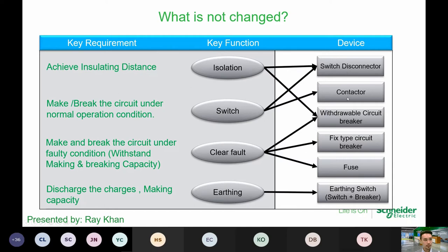So for the switch features, you will require a switch disconnector and also a contactor. Now, in the event of a fault, generally the whole key purpose of the switchgear is to clear the fault, right? In order to clear the fault, there are a few key components. One of them is the withdrawable or the fixed type circuit breaker, or you use a fuse, all right, to deploy this feature. And last of all, to discharge the charges of the making capacity, it requires earthing. Okay, so for earthing itself, it requires the earthing switch. All right, so these are pretty much just a run-through of the different components in a switchgear.